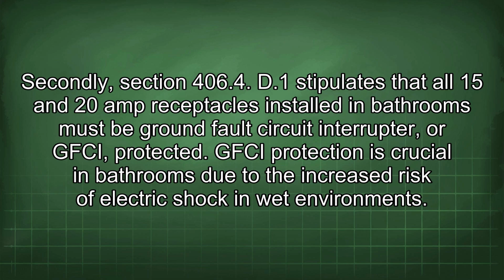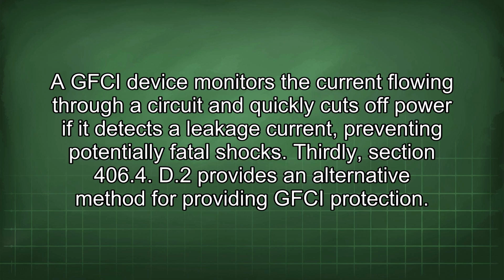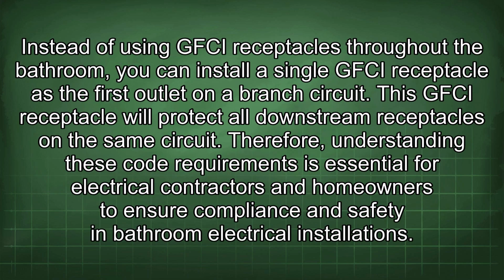(D)(1) stipulates that all 15 and 20-amp receptacles installed in bathrooms must be ground fault circuit interrupter, or GFCI, protected. GFCI protection is crucial in bathrooms due to the increased risk of electric shock in wet environments. A GFCI device monitors the current flowing through a circuit and quickly cuts off power if it detects a leakage current, preventing potentially fatal shocks. Thirdly, Section 406.4(D)(2) provides an alternative method for providing GFCI protection. Instead of using GFCI receptacles throughout the bathroom, you can install a single GFCI receptacle as the first outlet on a branch circuit. This GFCI receptacle will protect all downstream receptacles on the same circuit.